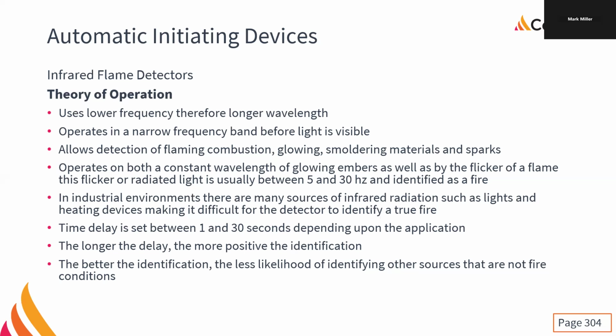Really, really sensitive, so we put a time delay on it. It's not like the time delay that we put for status change confirmation. We put a time delay between 1 and 30 seconds on, because it's going to react that fast. The longer the time delay, the more positive the identification. But if someone parks a vehicle and opens the door and you get reflected light off the door, that could set it off, because these are also much more sensitive to sunlight and light and heating devices. Infrared tube heaters, oh, totally set these things off. Absolutely an issue. Also, welders will set them off. So you've got to be careful with all that stuff.